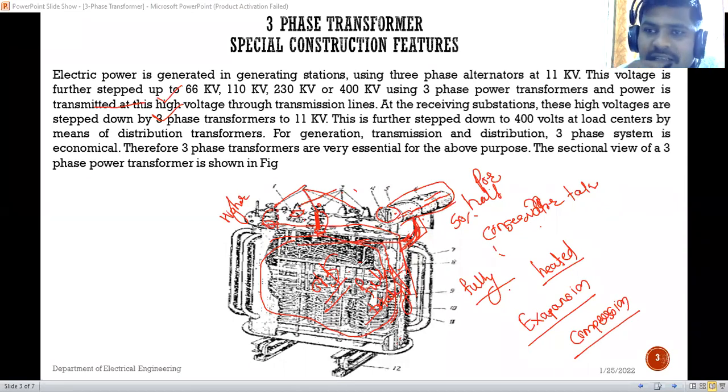Oil जर reduce झालं, what will happen? Transformer it is not fully filled राहील का? No, sir. So in that situation, to fulfill that requirement, a transformer should be filled fully. So the half filled conservator tank will pass the oil to the main tank of the transformer.